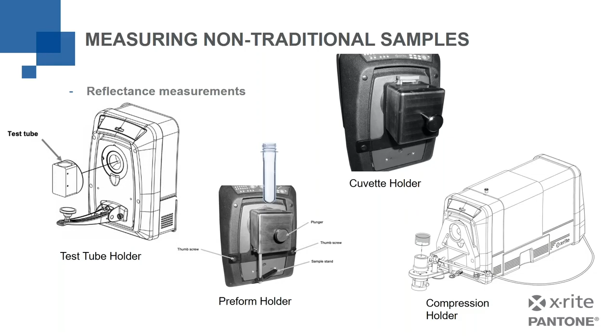It's kind of a complicated thing, but essentially it's used for either measuring fibers, which would go into this little cell, or you can also use it to measure carpet, where you actually put the piece of carpet up against the device. And what this compression arm does is control how much pressure is pushing against the fibers of the carpet when the measurement takes place. If you think about carpet, if you push harder or softer on it, you're going to bend it differently, and it's going to cause the color to shift. So it's really important to have consistent pressure when you're taking a measurement. So we have a device made to help control that.